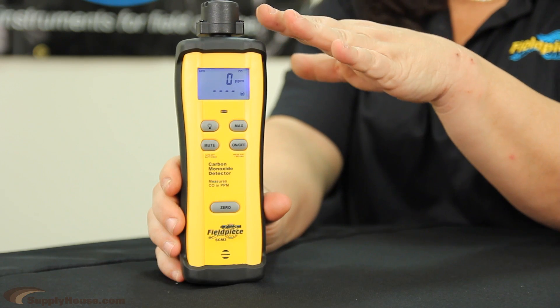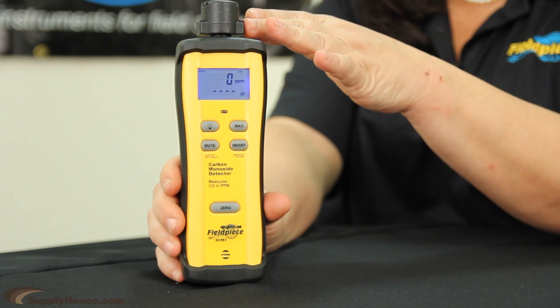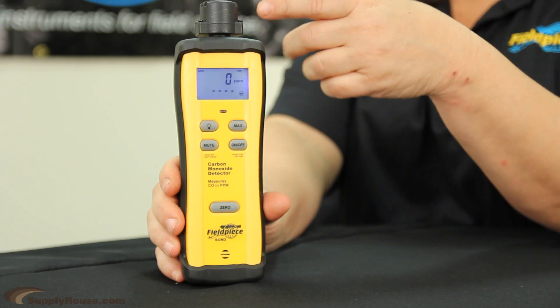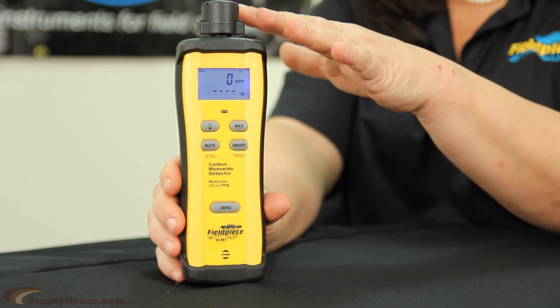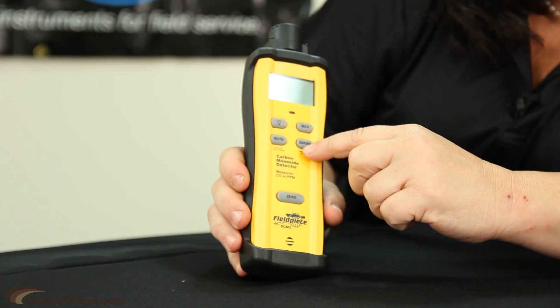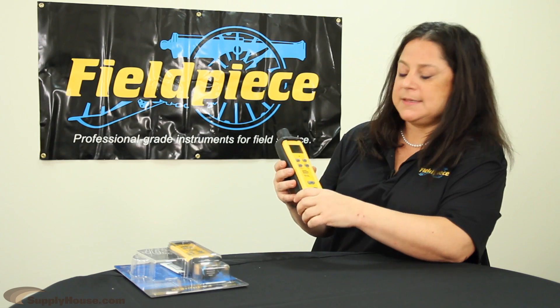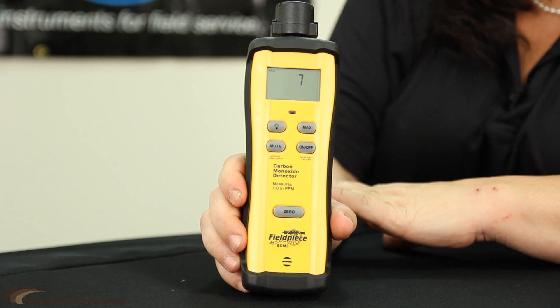The SCM3 comes with a very sturdy, rugged sensor that can be used for the walk-around test, or you can put a pump on top and get the level of carbon monoxide in the flue. You basically turn the SCM3 on and it takes about 10 seconds for the sensor to be calibrated.